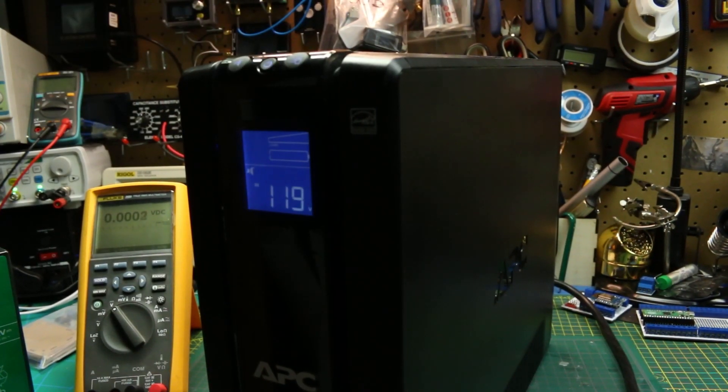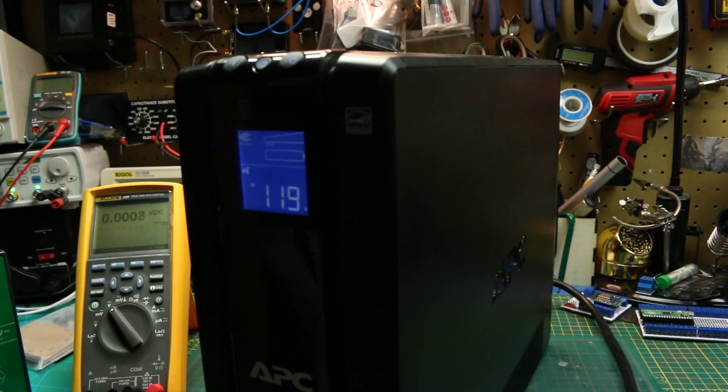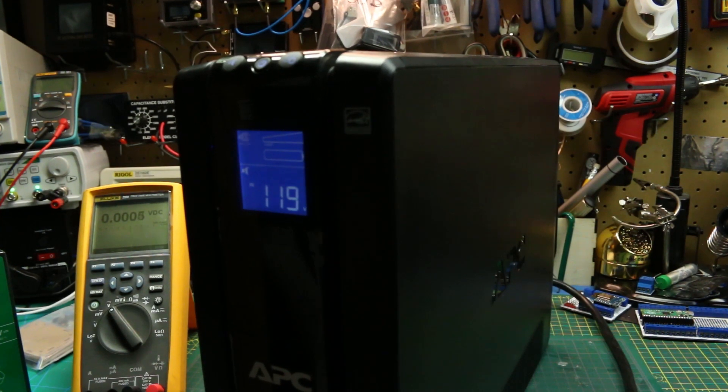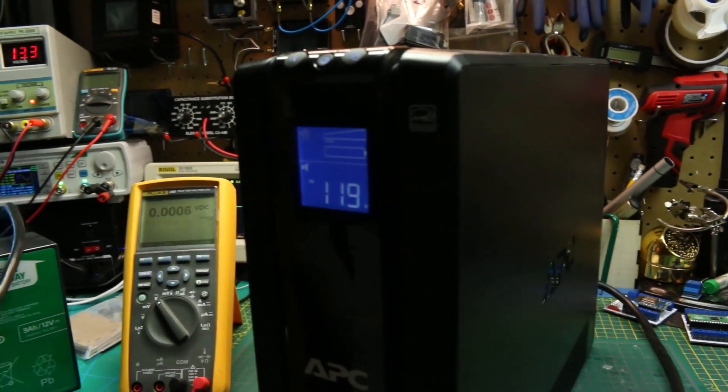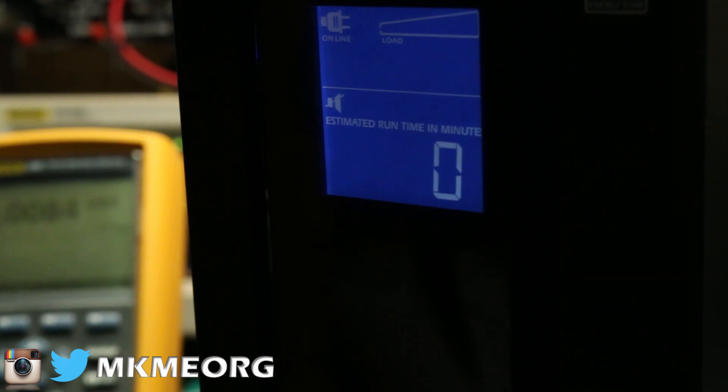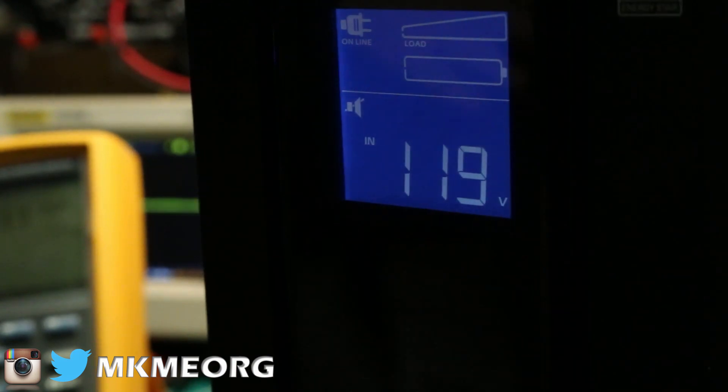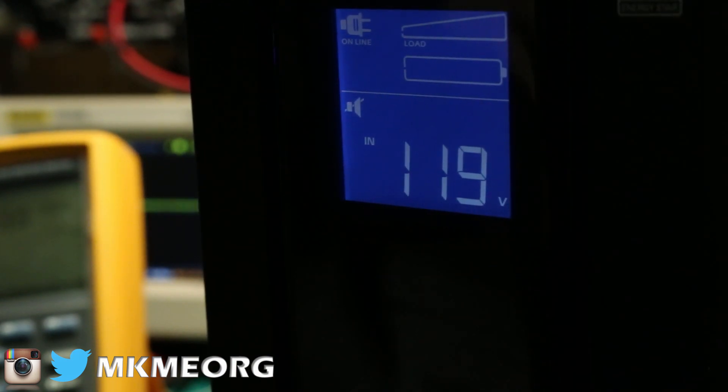And power up, no problem. Batteries are going to have to charge. They do have only a storage charge in them, they're basically flat dead. UPS recognizes that but immediately starts charging, no problem. It does flag them as it's a little upset about them initially, but this clears up in just moments and batteries charge away.